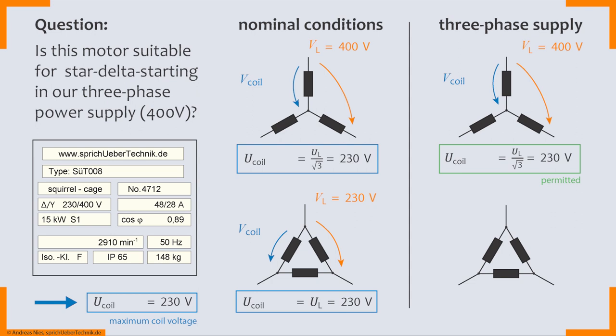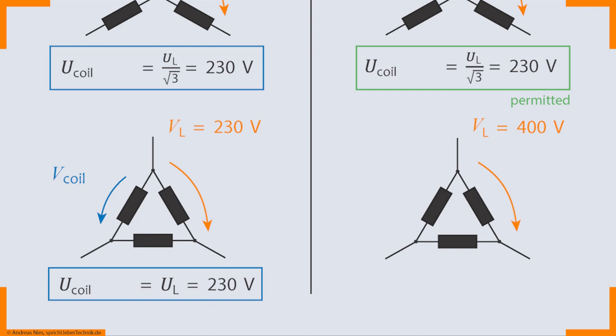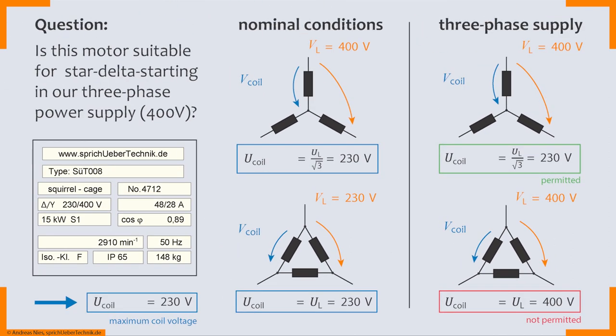But how about delta connection? Well, in delta connection we'd of course still have 400 volts phase-to-phase. And therefore the coil voltage would be just the same. It would just be 400 volts. And would this be okay? If you listened carefully until now you might know the solution already. No, of course it's not permitted. As you can see here on the left hand side the maximum coil voltage is 230 volts. So that's not going to work. And thus we cannot apply the star delta starting either. Which is the correct answer to the original question?